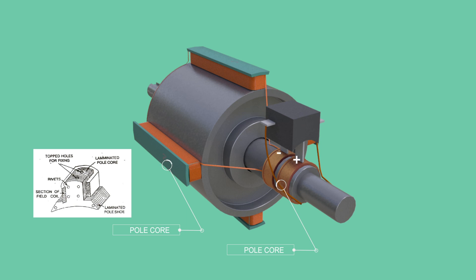If the rotating coil method were used, slip rings would have to be fitted along with the armature coils in order to collect electricity. But transferring such high-voltage electricity with slip rings is rather impractical. It is quite possible to transfer low-voltage DC excitation current with slip rings.